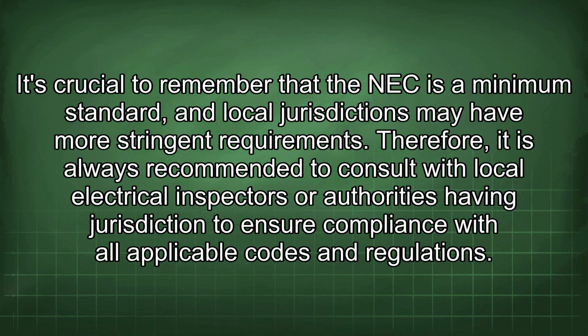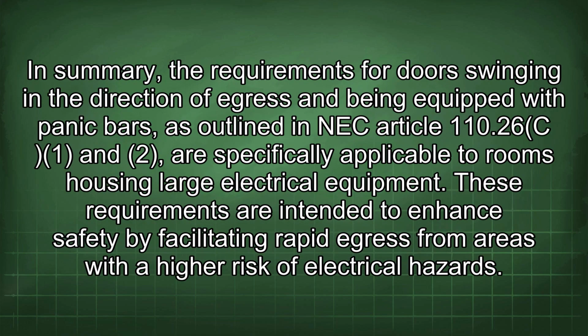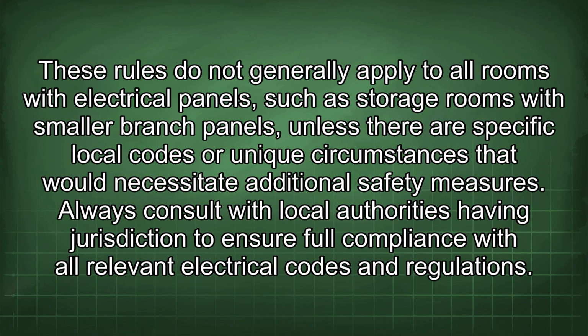applicable codes and regulations. In summary, the requirements for doors swinging in the direction of egress and being equipped with panic bars, as outlined in NEC Article 110.26(C)(1) and (2), are specifically applicable to rooms housing large electrical equipment. These requirements are intended to enhance safety by facilitating rapid egress from areas with a higher risk of electrical hazards. These rules do not generally apply to all rooms with electrical panels, such as storage rooms with smaller branch panels, unless there are specific local codes or unique circumstances that would necessitate additional safety measures. Always consult with local authorities having jurisdiction to ensure full compliance with all relevant electrical codes and regulations.